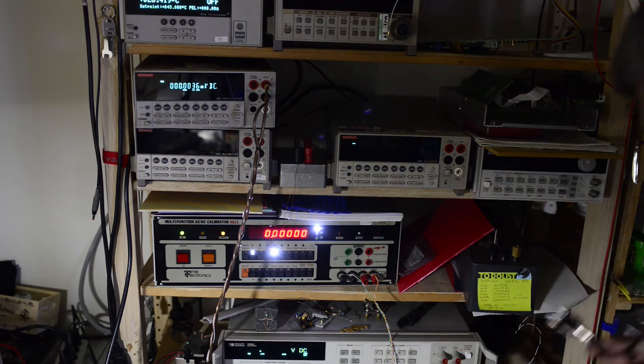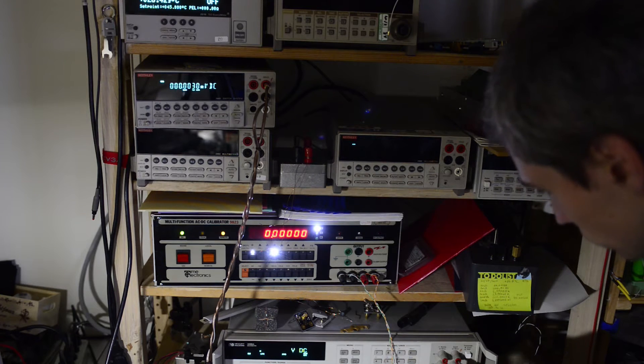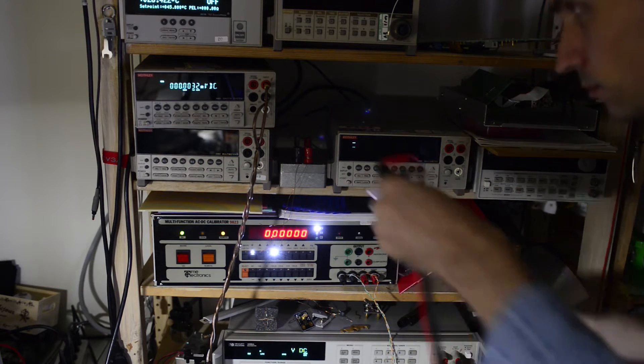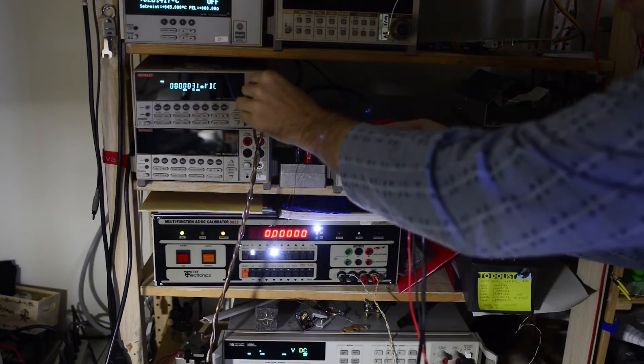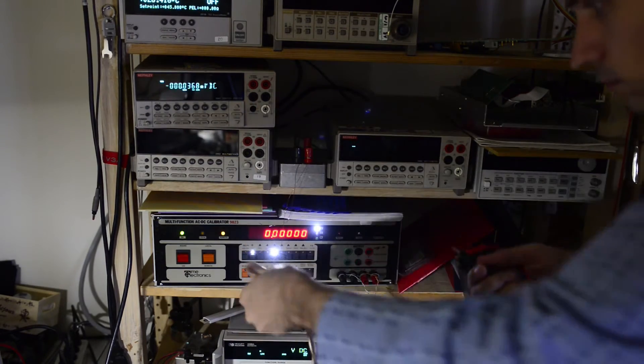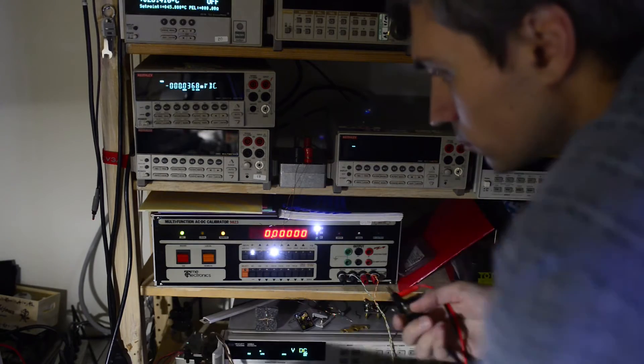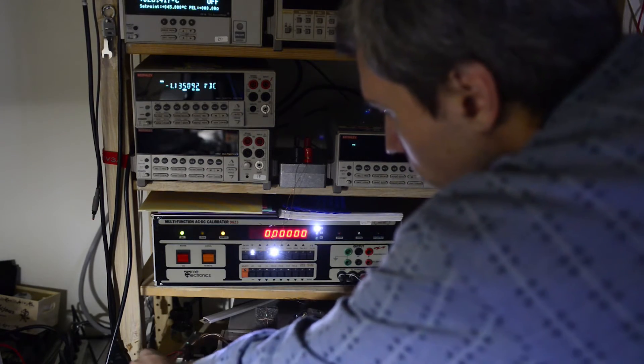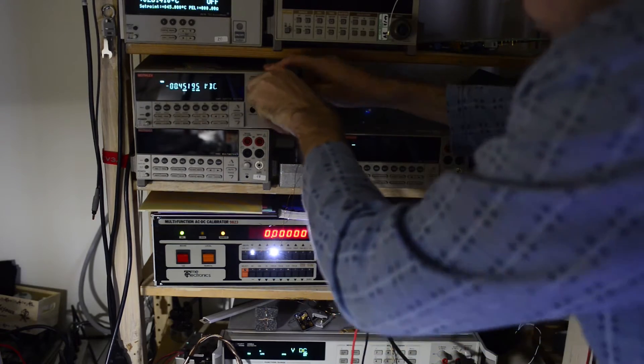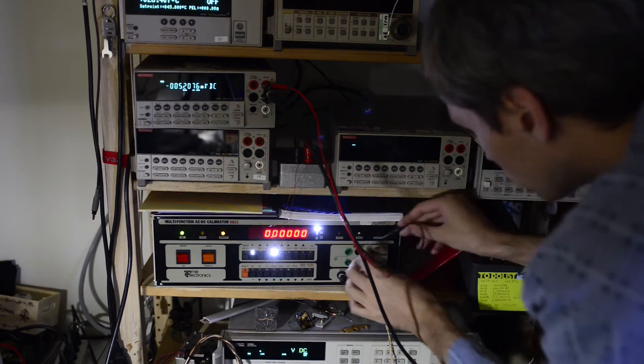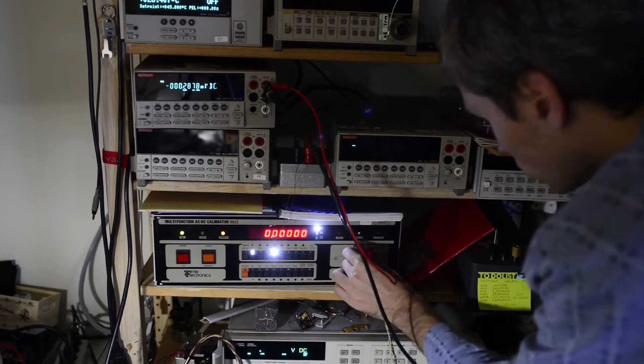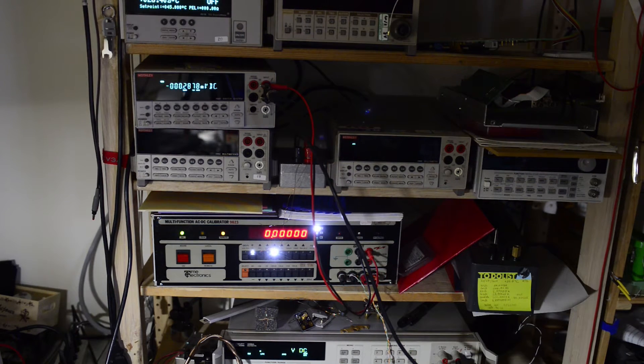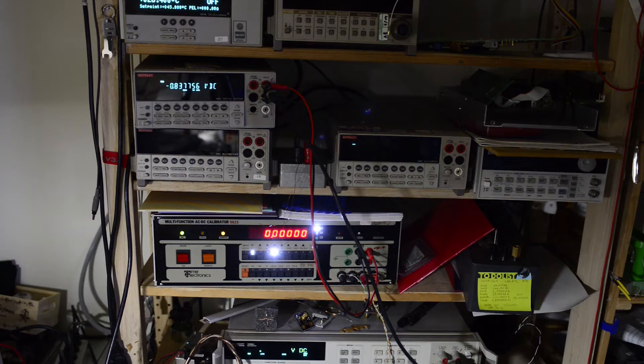Also for high voltage testing I need to change the output terminals on Time Electronics calibrator. So now I'll switch output terminals to high voltage output. The calibrator needs a few seconds time to ramp the high voltage, so I have an 8 second delay before taking any measurements.